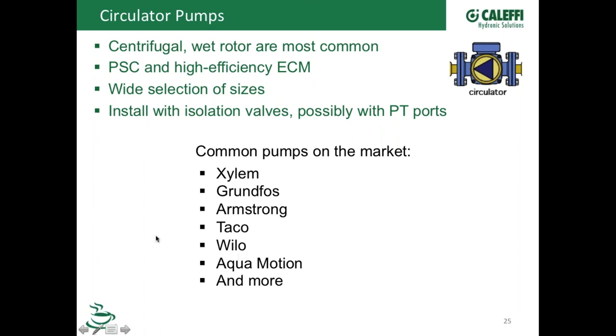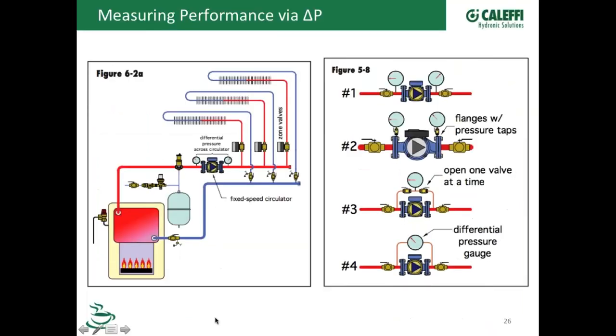A couple of things I would always encourage you to do when you put a pump in is put isolation valves on both sides of it. Someday somebody's going to have to work on that pump or change it out, and having a couple of $20 worth of valves can make it so much easier for the next guy to get in there and work on it.